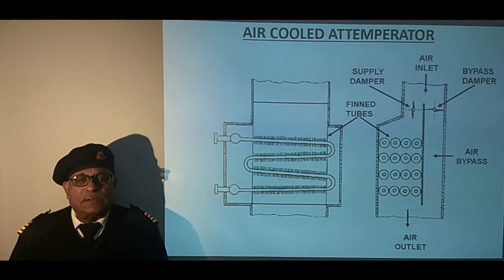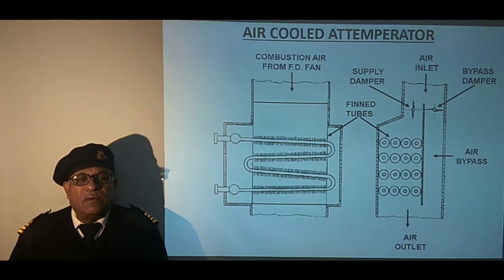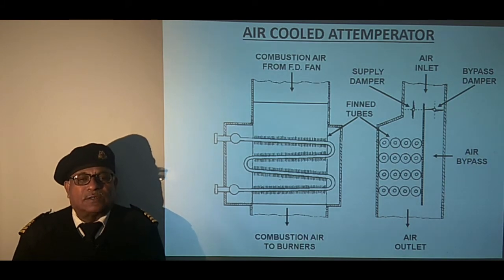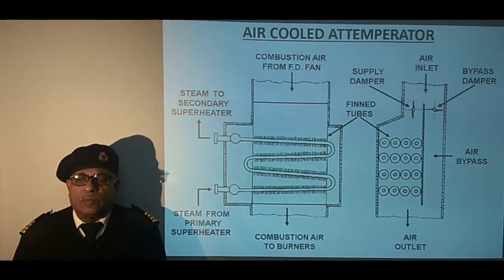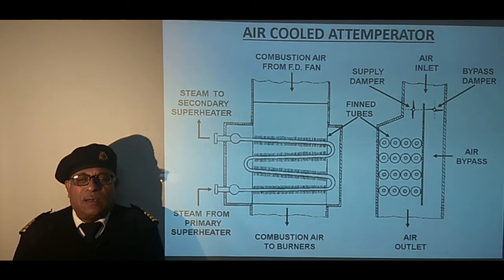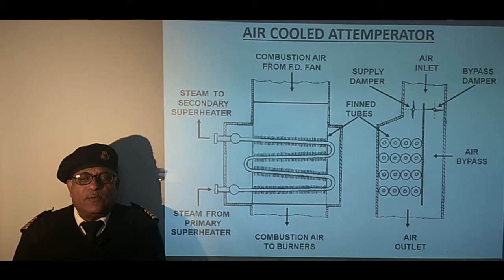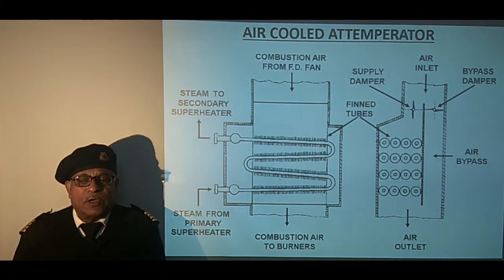This is the air outlet to the burners. Steam from the primary superheater enters from the bottom connection to the header. It consists of a W-shaped finned coil arranged in the combustion air path between the primary and secondary superheaters. To control the final temperature of superheat, link dampers are used to control the supply of combustion air through the attemperator or to bypass it.